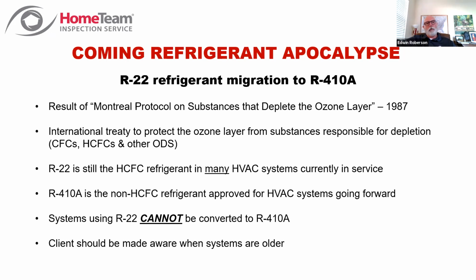Now, the thing about it is those systems that were designed to use R22 cannot be converted to R410. And when you're looking at an older system, especially when you're getting into 15 and 20-year-old systems, clients should be made aware when the systems are older. If you're talking about a 15 or 20-year-old system, it's outlived what the HVAC guys say you would get out of it anyway. So a lot of this where we are today will take care of itself very soon.